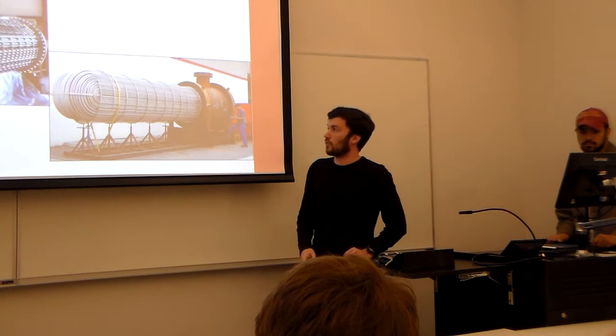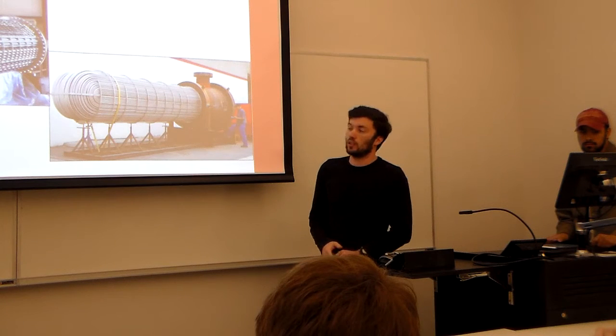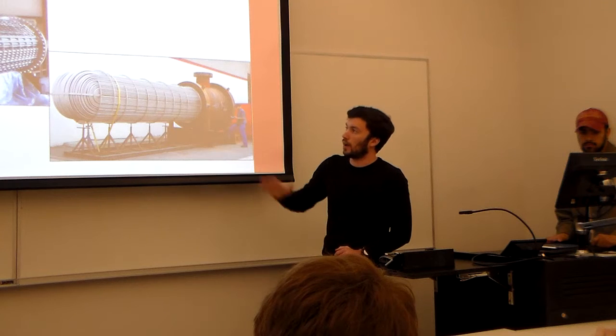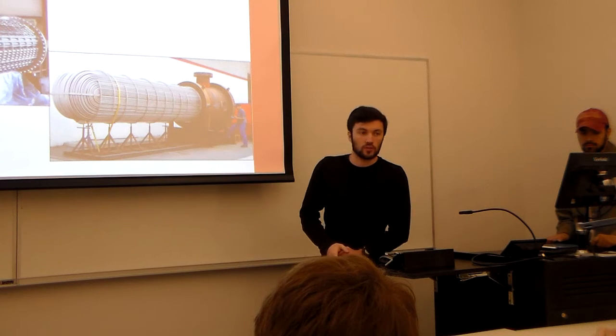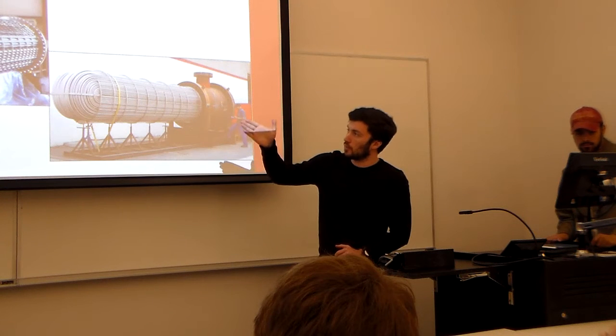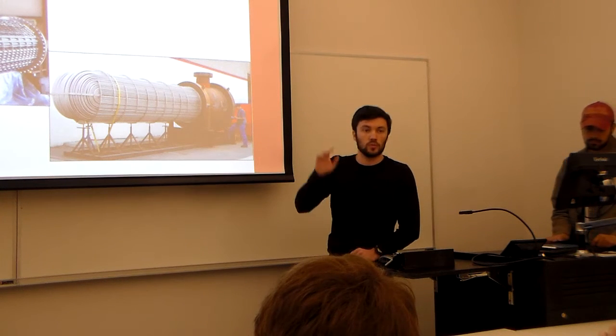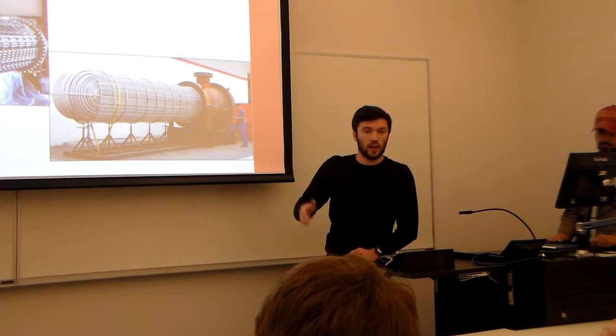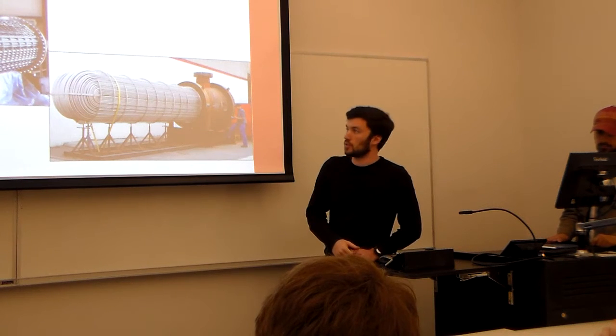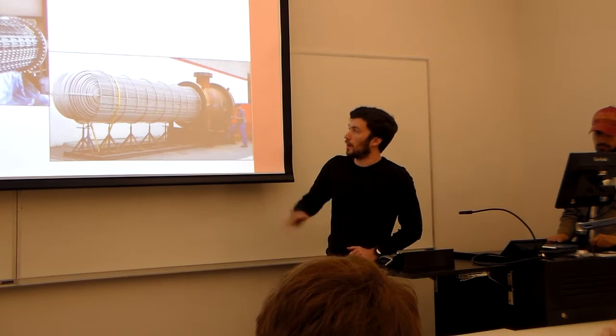So this is the basic form of a shell and tube heat exchanger setup. The left one is not actually a U-tube. I basically gave us that picture just so you can see the process of how it's assembled. You have baffle plates that support the tubes. The tubes are slid into place during manufacturing and are typically welded on the ends to hold them down.